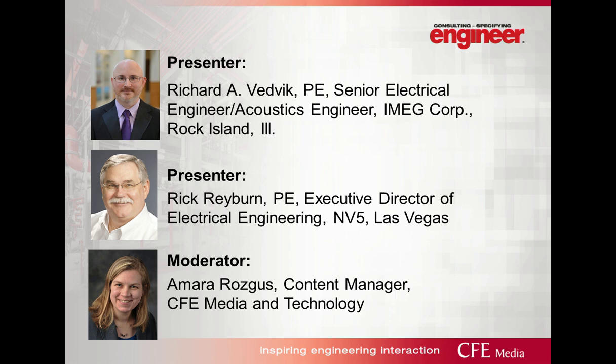Good question. This is kind of a loaded question too, because first off, you've got to define the building. If I have an office building that's similar to the one I'm sitting in right now, which is maybe 10,000 square feet, and the client, upon design purposes, says, I want to have my entire building on, I never want it to go down. I want it to be on generator power all the time. So the engineer designed a generator to back up the entire building.